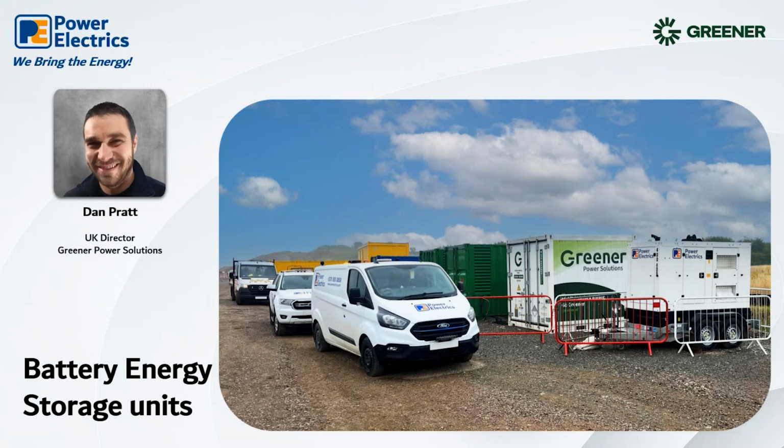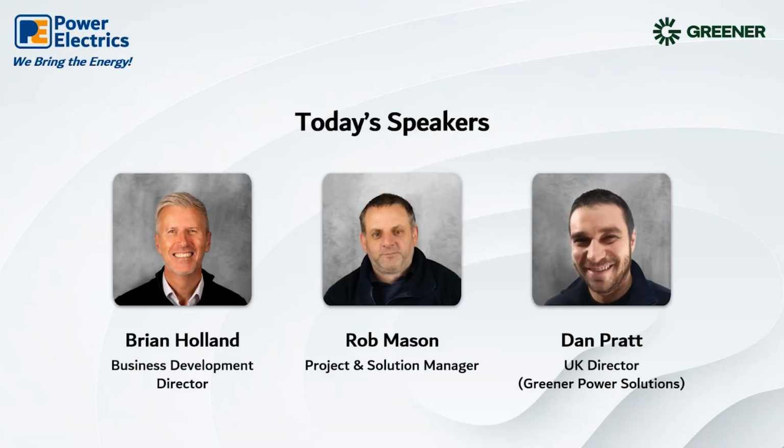If there is a 250 kilowatt energy source, such as a 350 kVA diesel generator connected to the battery as a charging source, but at the time the average load is around 125 kilowatts, that load would put the battery inverter at 50%. When the generator is started to recharge, although the generator will be running at 250 kilowatts, the battery in this instance will only be charging with the delta of 125 kilowatts, which in this case will result in a full charge within 2 hours.